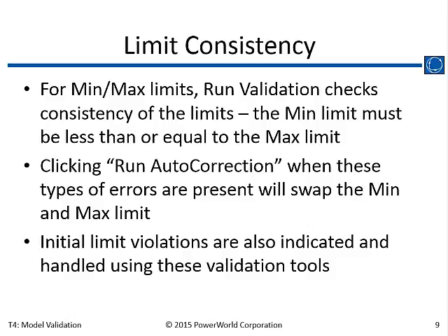Like that example we talked about with the VR on an exciter. VR is a calculated state. If it's above its limit, there's an option that it'll automatically change the limit, but that's just a temporary change, because the next case you run, the VR might be different. It might be below its limit.